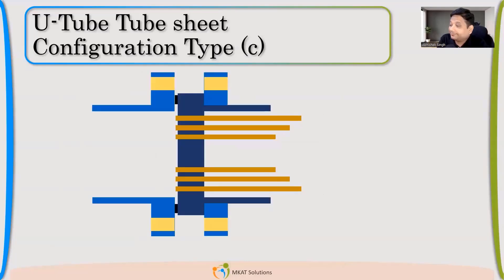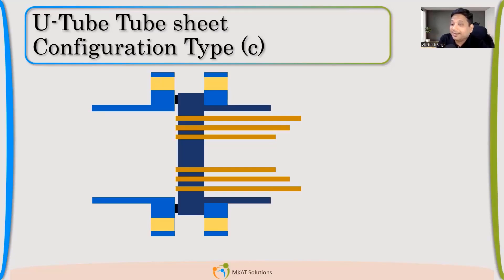Now C — it is still integral with shell, but what is the difference between B and C? In B, the tube sheet was extended as a flange. In C, it is not extended — it is a lap joint. It's not sandwich type. It may be a slip-type. So this is Type C: tube sheet integral with shell but not extended as a flange, using a lap joint instead.